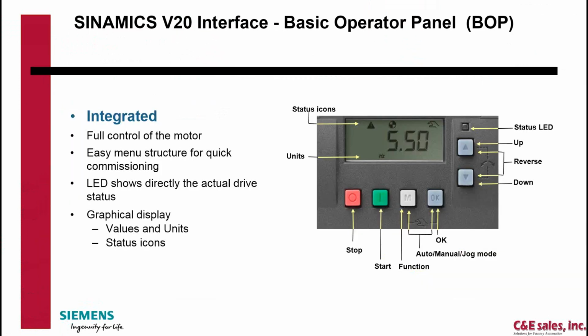Built into the V20 is this basic operator panel, or the BOP, as it's the common term in Siemens. Again, it's integrated into the front of the drive. Before this Smart Access module, this was the only way to really parameterize the V20. So, pushing buttons, there is no software for it. There is a way to replicate through an SD card and a module, but that's just going to copy parameters from one drive to another with the exact settings.